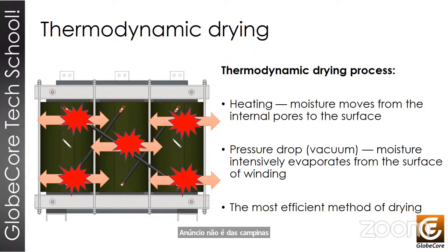Inside the insulation, moisture moves in the form of vapor from the spots with a higher content to the spots with a lower content, and from the spots with a higher temperature to the spots with a lower temperature. Therefore, in order to accelerate the movement of moisture to the surface of the insulation, it is necessary to ensure fast and good heating of the entire active section of the transformer.